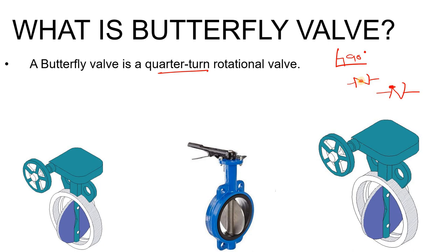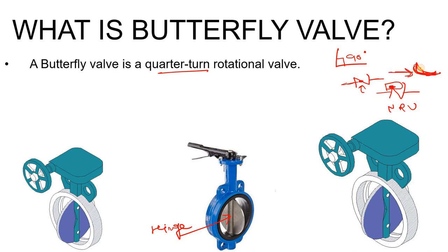If you compare it with the P&ID symbol of the check valve, the dotted line placement is different. In the butterfly valve the hinge is at the center, whereas in the NRV (non-return valve) the hinge is at the top — it operates like a flapper type, opening when pressure is applied. You can check our videos about NRV where we have explained many types.